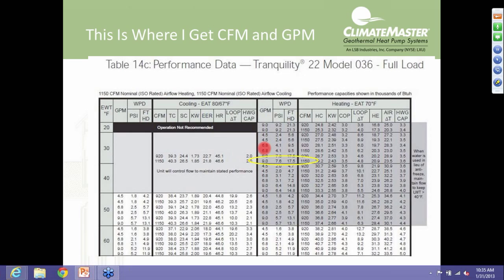We've got 3 different GPMs that we can commission it to: 4.5, 6.8, or 9. So again, we're going to run that pump percentage up until I can see 9 gallons per minute on the screen. Or if it's outside of that range, or I'm working with a modulating valve, I can go to WPD, water pressure drop, and under PSI I'd be looking for a pressure difference of 7.6 PSI with my digital tire pressure gauge, using those pressure ports on the front of the heat pump.